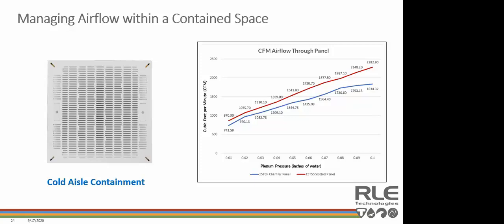Once you know you have enough cooling to satisfy the total IT load in the room, it's important to know how much of that cold air each aisle should get. Again, using a rule of thumb calculation can help ensure that enough air is being supplied to each aisle. For most rack-mounted equipment, 125 CFM per kilowatt of IT load can be used to calculate how much airflow is required for a given rack or row. Again, this is a rule of thumb calculation. We're not going to get into all the factors that affect the actual determination in this presentation, like altitude, temperature differential, and supply air temperature.